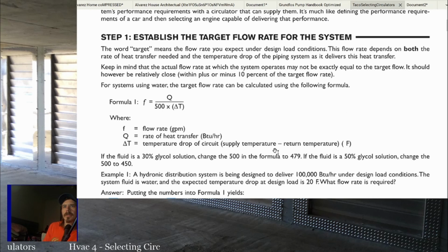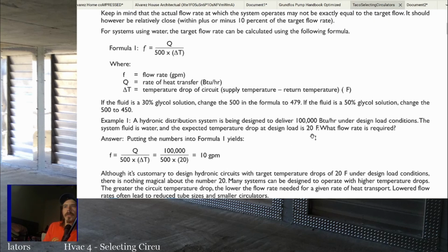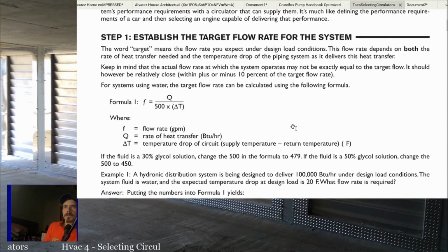And the other thing you'll need to know as we get down here is the temperature drop in the circuit. So it's pretty common to go for a temperature drop of 20 degrees. I will say this. I mentioned it a little bit last class, but for higher efficiency boilers and things like that, it's usually not a bad idea, especially if you're going to be running at a higher temperature, to have a slightly bigger temperature drop sometimes. The colder return water temperature helps out in their efficiency. But in general, a lot of systems are designed for a 20-degree or so temperature drop.